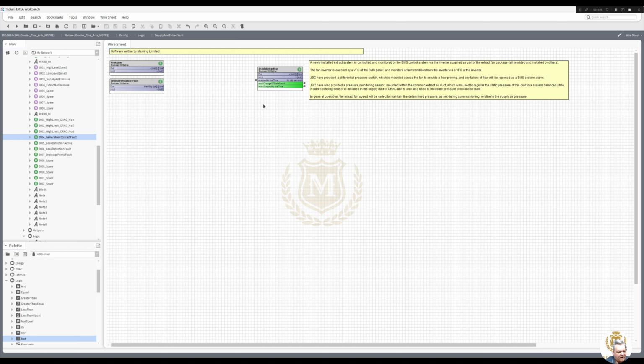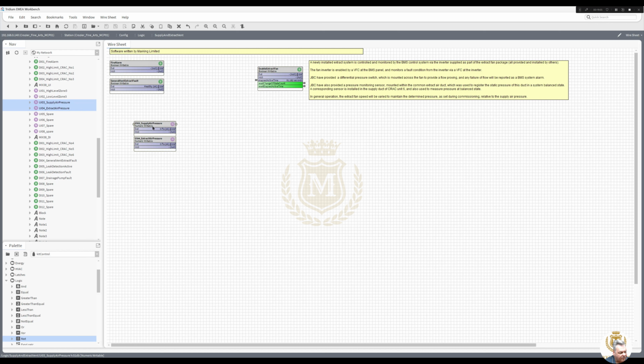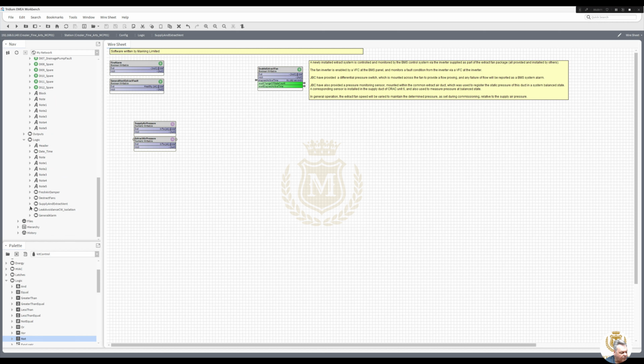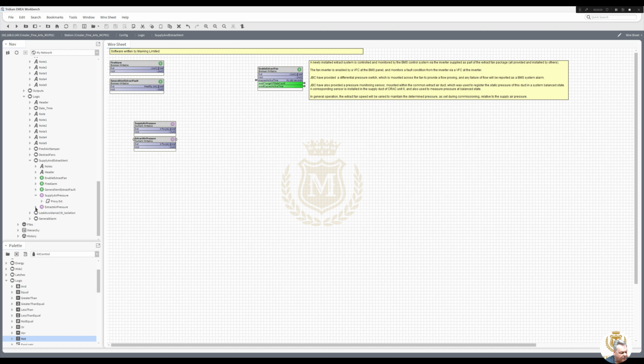And then we need an enable. So we've got the fault, we've got the fire alarm. Will be coming into this folder. So differential pressure switch to define the flow proving. So let's go and get these differential pressure switch, supply and extract pressure. Copy, paste, rename, take out that. Rename, take out that. I'll just open up the folder down here, remove the numeric history, remove from numeric history because you don't want it twice.